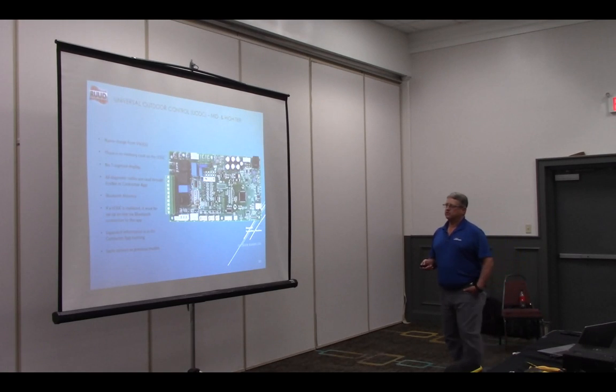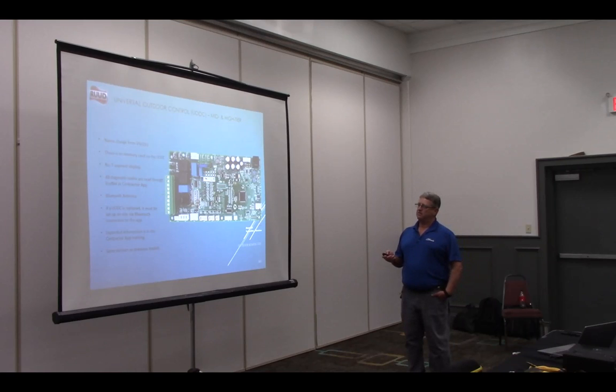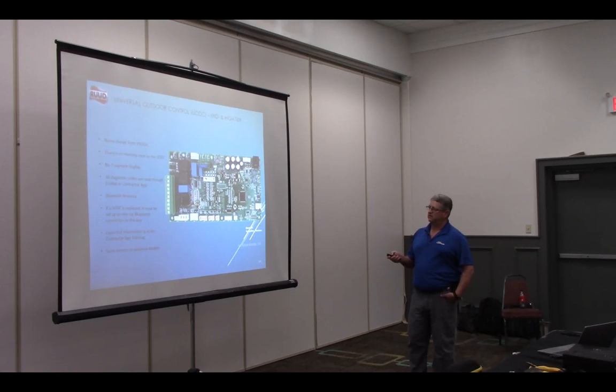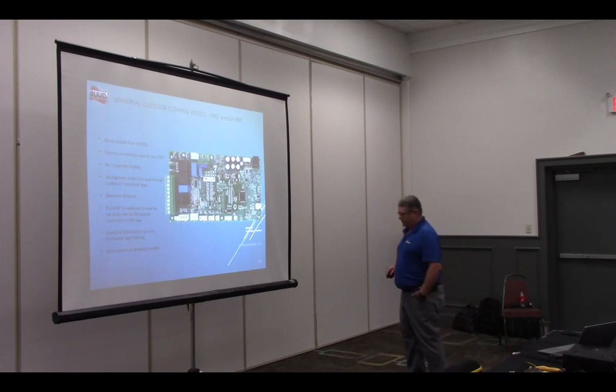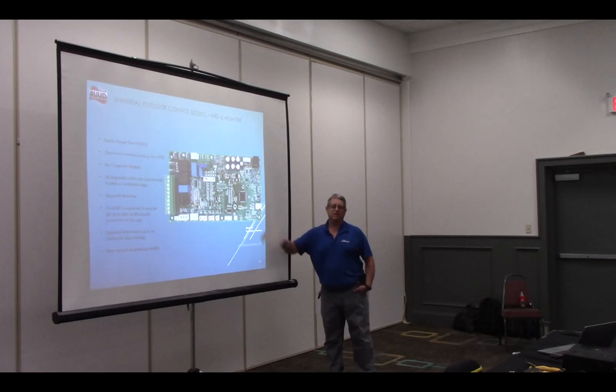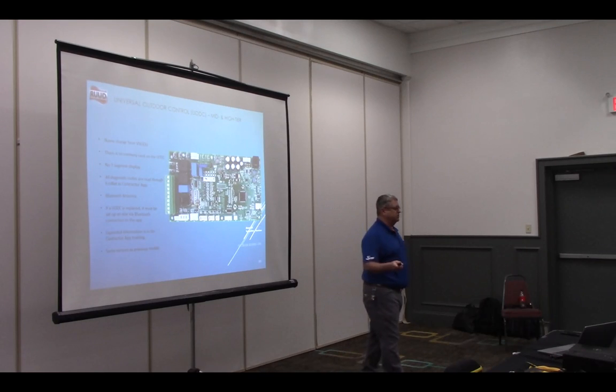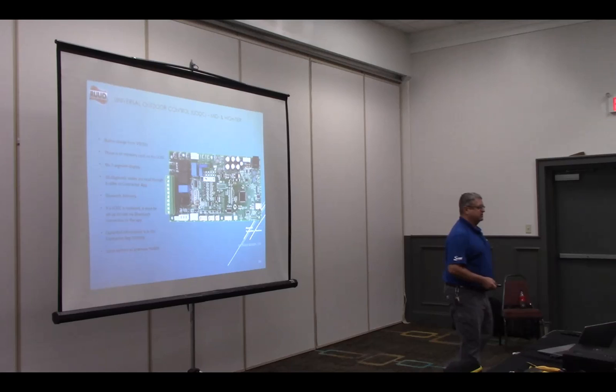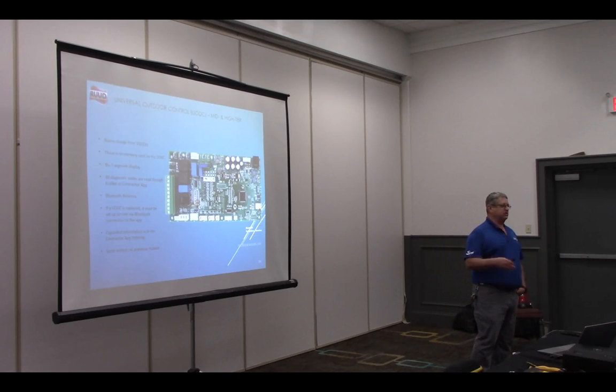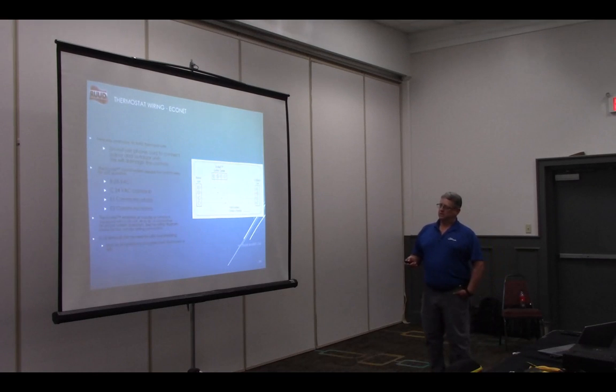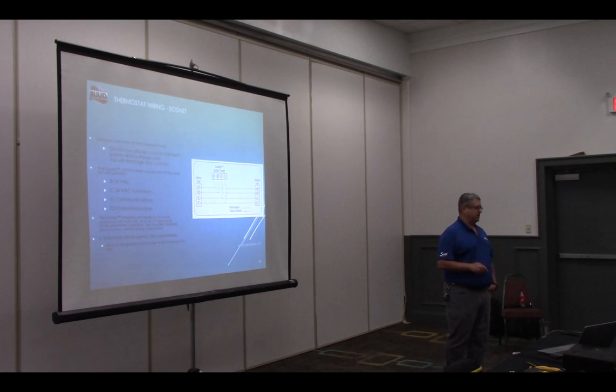The high tier boards, just remember, have no memory cards anymore, no dip switches, everything. This is what our Bluetooth antenna looks like here. Let's say it becomes damaged. If you get close enough to it, it still will work. You usually have to take the door off, but it should get you working so you can troubleshoot the system. 18 gauge control thermostat wire. You cannot use phone cord or anything like that. 18 gauge thermostat wire. It does not have to be shielded.